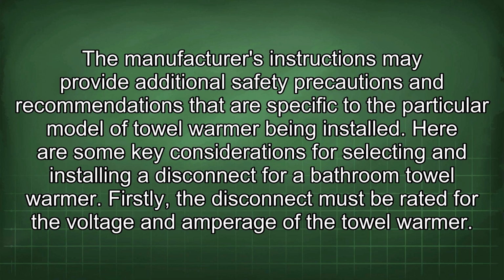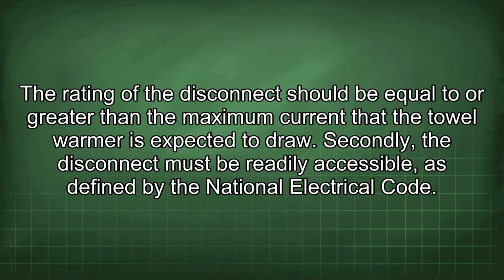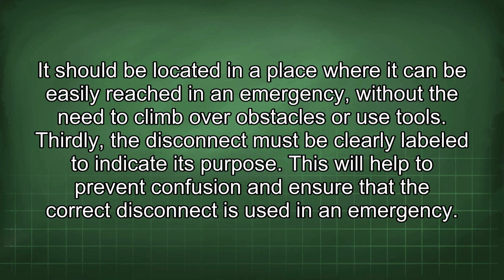Here are some key considerations for selecting and installing a disconnect for a bathroom towel warmer. Firstly, the disconnect must be rated for the voltage and amperage of the towel warmer. The rating of the disconnect should be equal to or greater than the maximum current that the towel warmer is expected to draw. Secondly, the disconnect must be readily accessible, as defined by the National Electrical Code. It should be located in a place where it can be easily reached in an emergency, without the need to climb over obstacles or use tools. Thirdly, the disconnect must be clearly labeled to indicate its purpose. This will help to prevent confusion and ensure that the correct disconnect is used in an emergency.